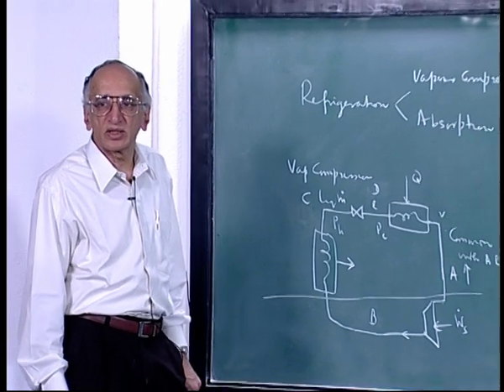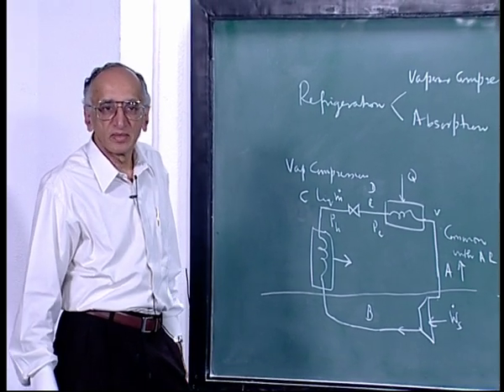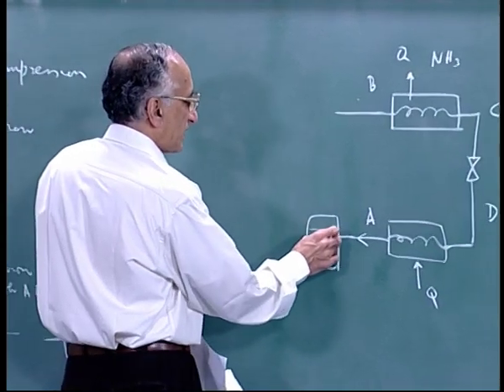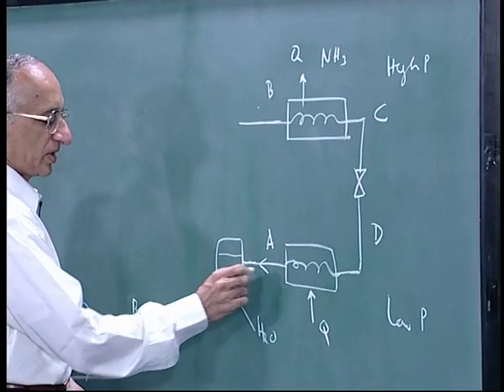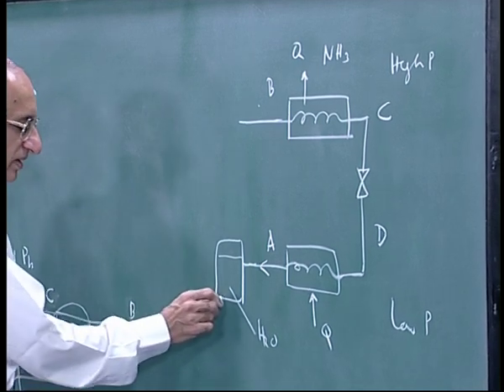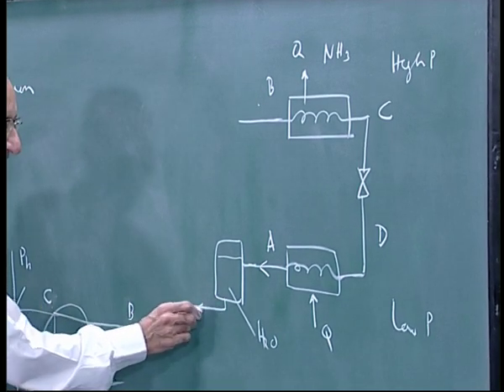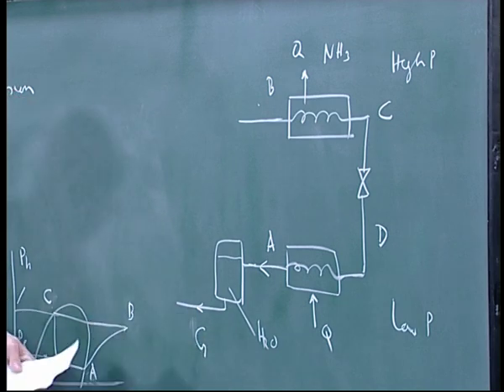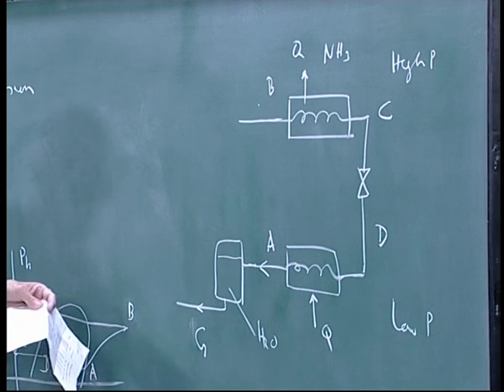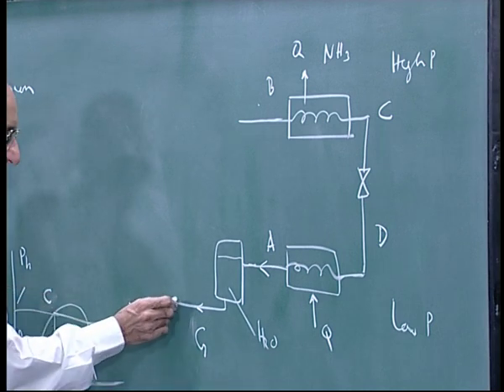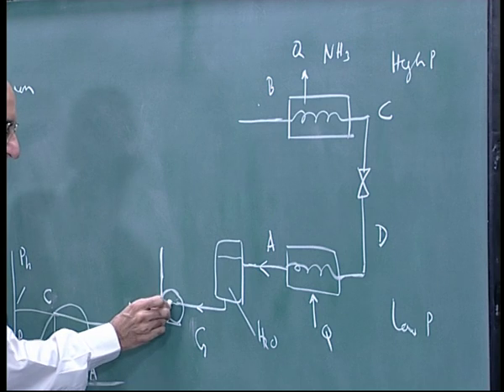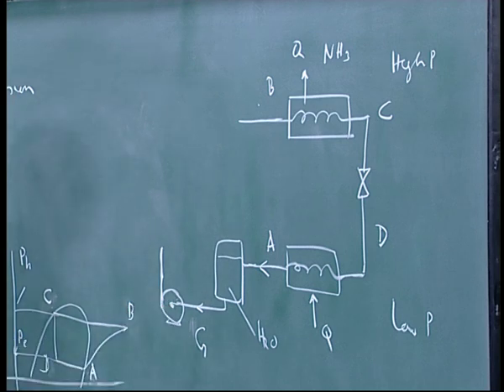Instead of using a compressor, absorption refrigeration works differently. Compressing a gas requires much more energy than pumping a liquid, and you also take advantage of enthalpy changes during absorption. Water is present, and the ammonia coming in is absorbed into it, so a concentrated solution of ammonia is taken out. This concentrated solution is then pumped — using a centrifugal pump — up to what is called a generator.